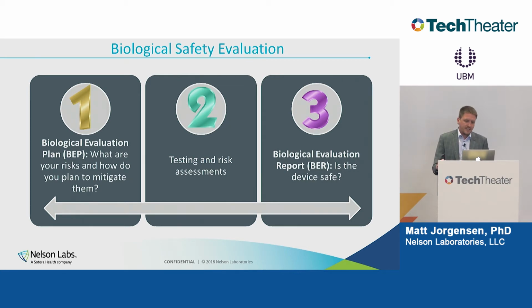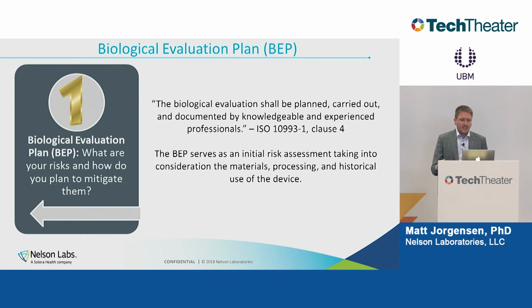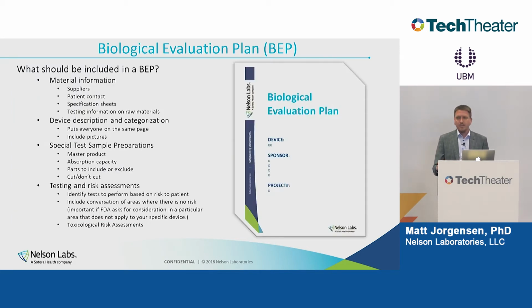So we'll talk about each of these three steps. I've mentioned the biological evaluation plan already. One of the main benefits of making a biological evaluation plan is that it gives you the opportunity to check with the FDA as part of a pre-submission process whether or not they'll agree with your strategy up front. This can be a huge time saver down the road.